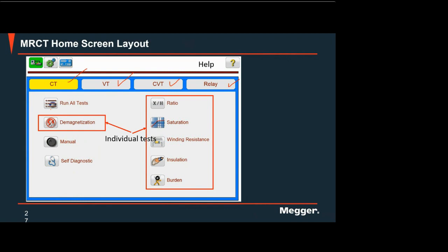So for example, it will do the winding resistance first. But because we inject DC current on the winding resistance, it will do the demag first before the saturation curve or before the ratio test. So I would really suggest to run all tests because the MBCT or the MRCT will do the tests in sequence. It knows what to do first, right?